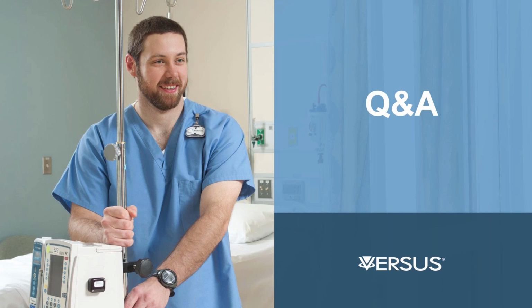So at the same time, so I don't miss the purpose of the question, in the IV pumps scenario I talked about, the project, we kept in touch with the supply chain folks, IT, and biomed, because they each had a small part to play. When new equipment was brought in, the biomed folks would actually affix the locator tag to it. They would enter it into the system. So making sure that they continued to have what they needed to perform those tasks. Supply chain was those folks that we depended on to make sure that equipment was moved around by using that technology. So we continued to engage.